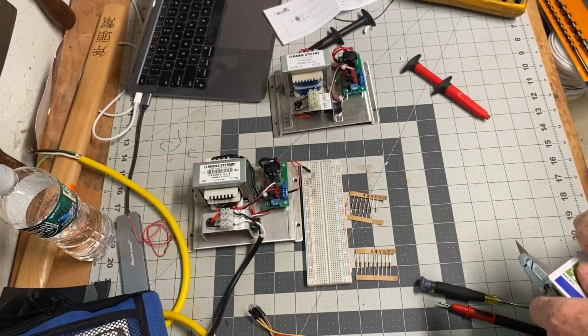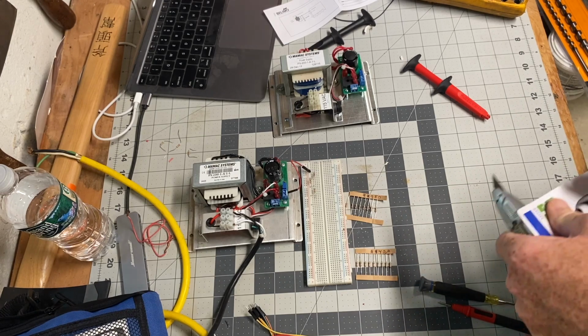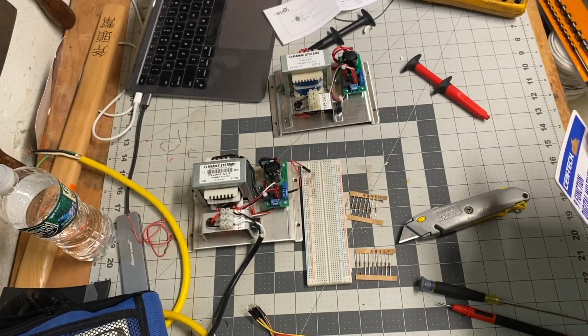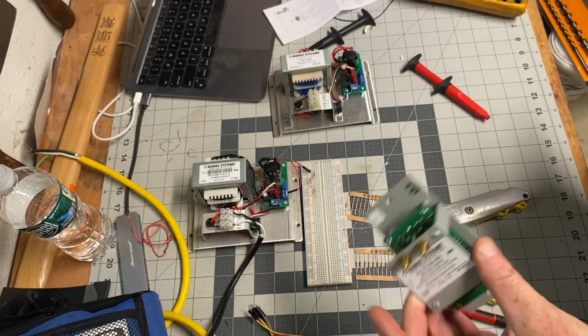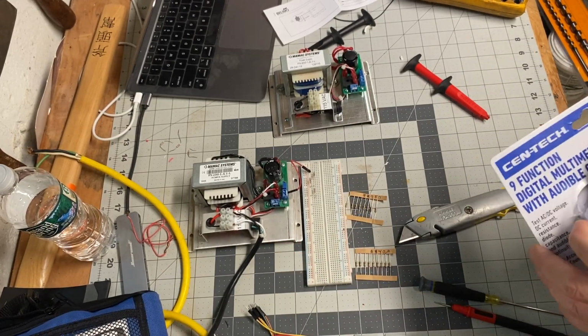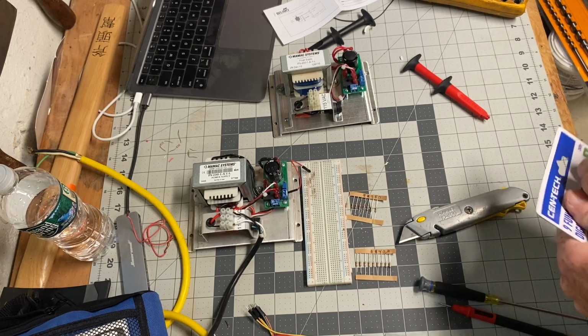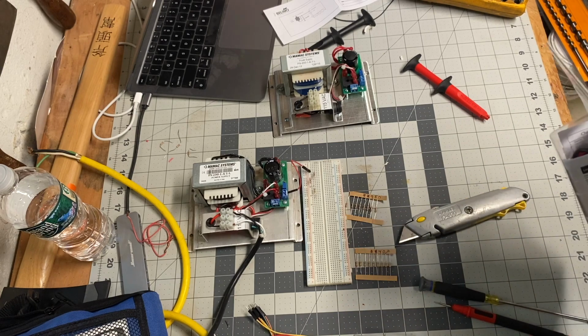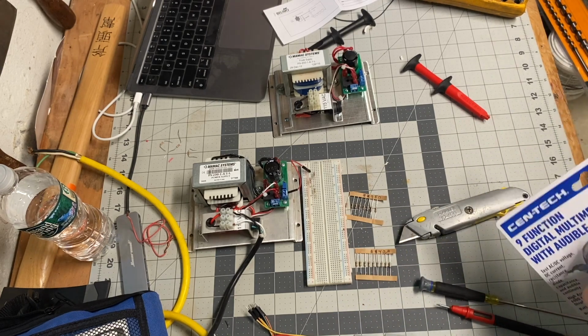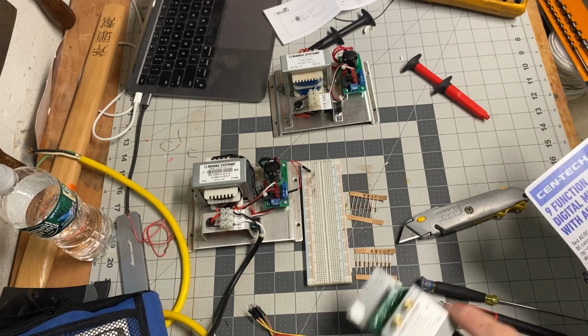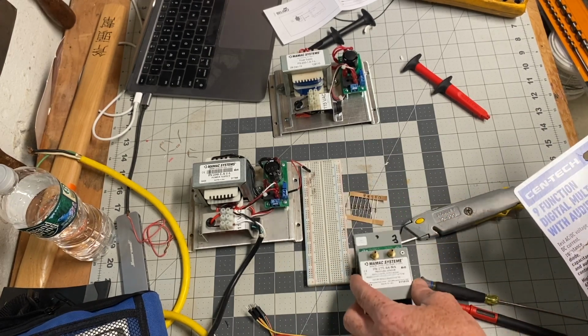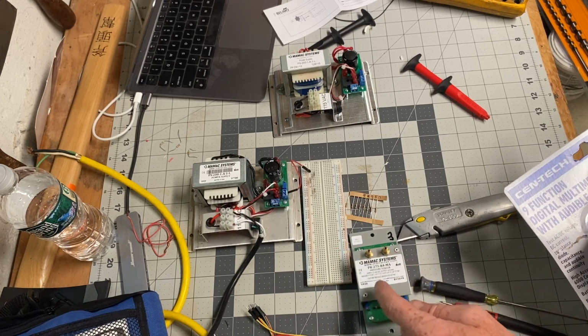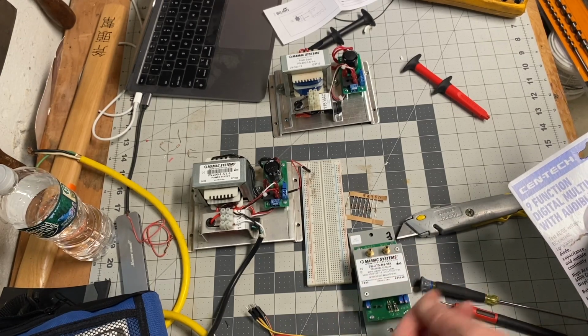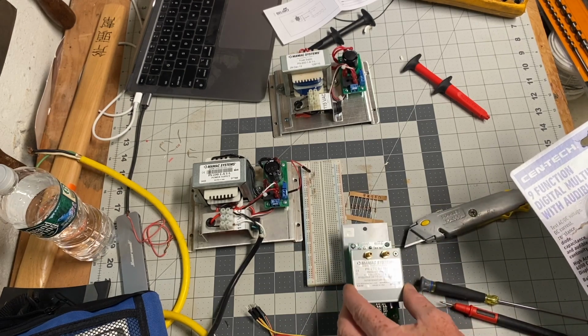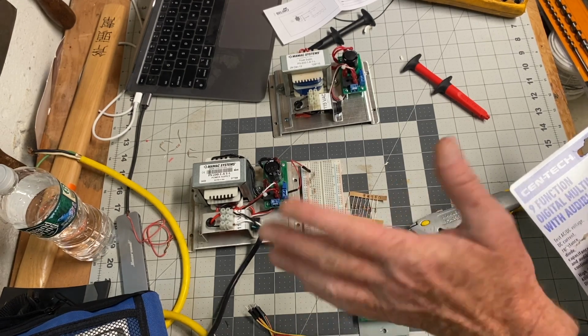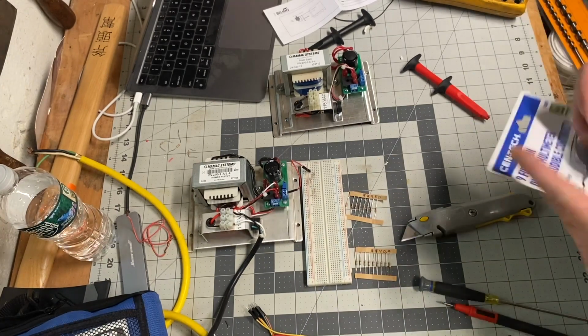What happened was I've been having problems. I work on building automation systems, and we've had a DP sensor for a building that was not giving a good reading, and it was low, and when we verified it, it wasn't low. The milliamp readings coming off were fluctuating and really on the low side. When you're using a DP sensor like this for building pressure, disconnect the tubes, and the sensor set up to read both a positive and negative number, it was reading about 4 to 5 milliamps rather than 12 milliamps. It should have been reading 12.